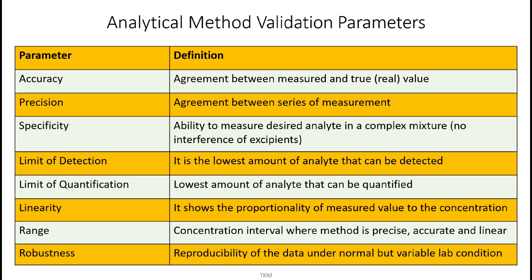Accuracy is the agreement between the measured and true value. Precision is the agreement between a series of measurements. Specificity is the ability to measure the desired analyte in a complex mixture. Limit of detection is the lowest amount of analyte that can be detected. Limit of quantification is the lowest amount of analyte that can be quantified. Linearity shows the proportionality of the measured value to the concentration range. Range is the concentration interval where the method is precise, accurate, and linear. Robustness is the reproducibility of data under normal but variable lab conditions.